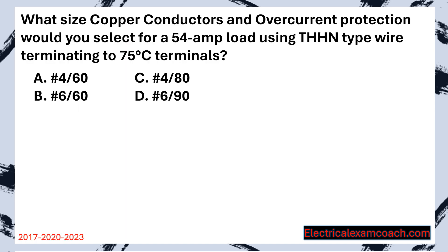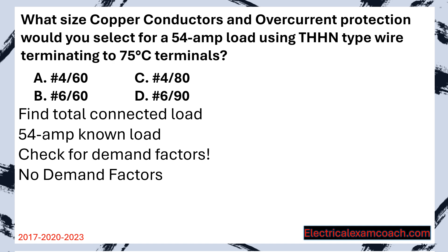What size copper conductors and overcurrent protection would you select for a 54 amp load using THHN type wire terminating to 75 degrees C terminals? Step one: find our total connected load. In this case it's 54 amps, but we must check for demand factors. They've not mentioned a specific piece of equipment or that it's going to run for three or more hours, so there are no demand factors. Now we size our overcurrent protective device first — we head to table 240.6A for a 54 amp load and choose the next standard size up, which is a 60.